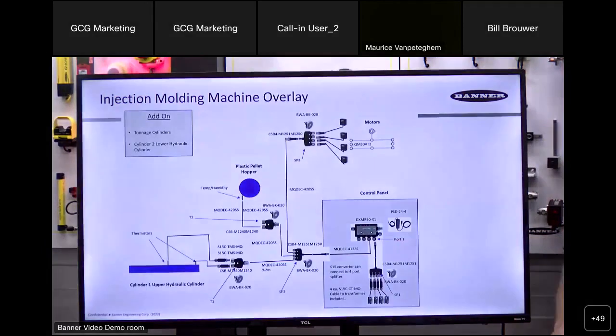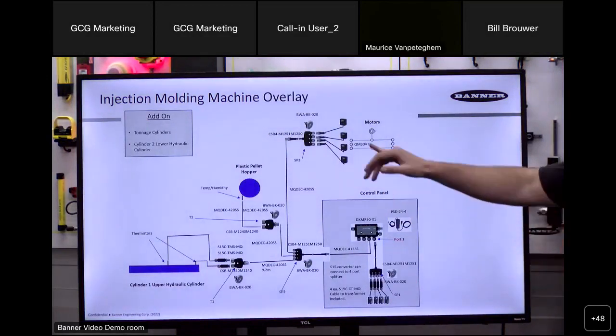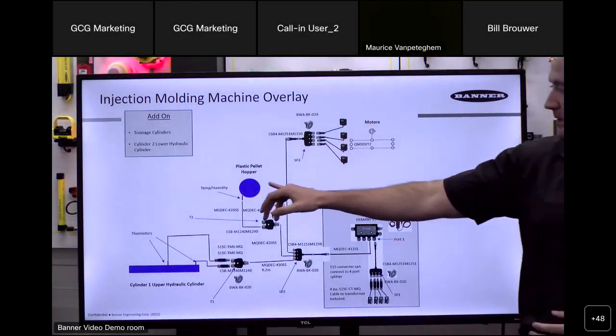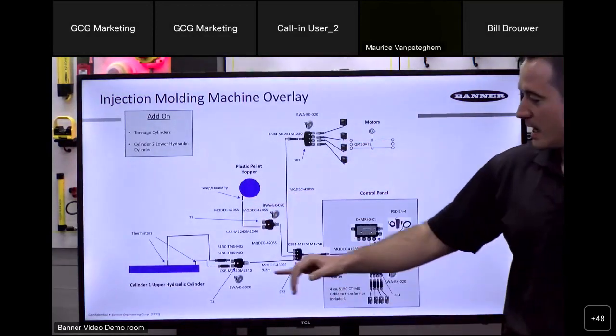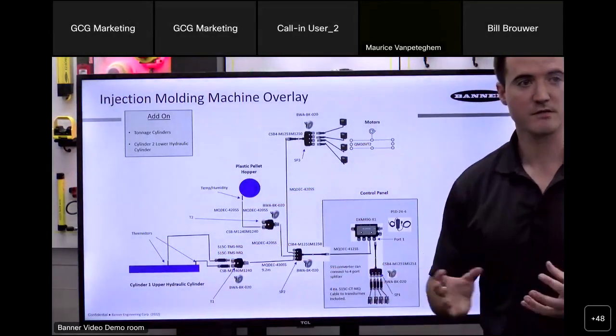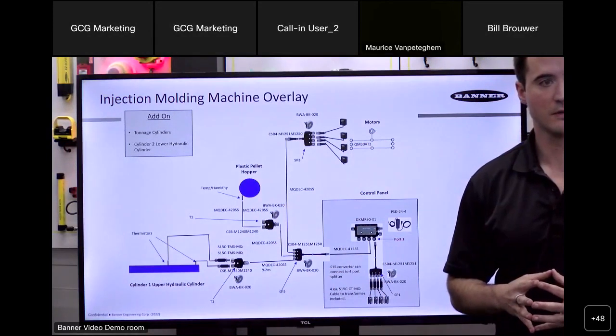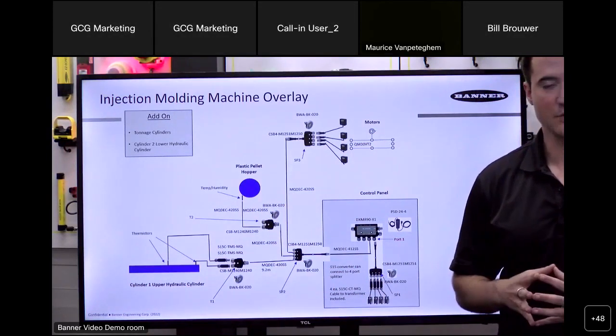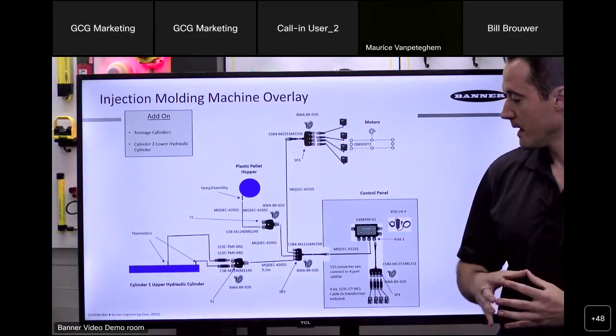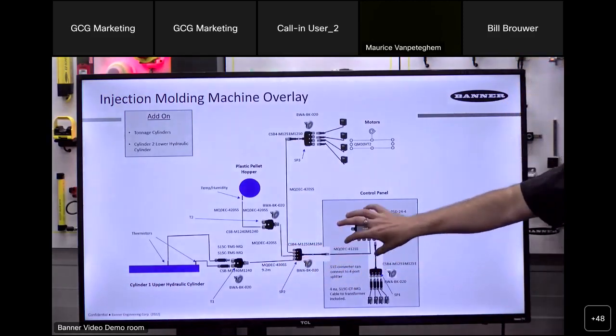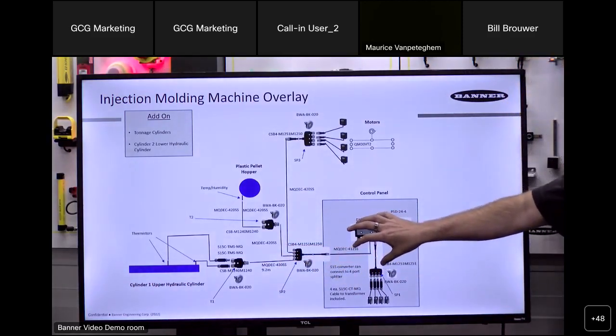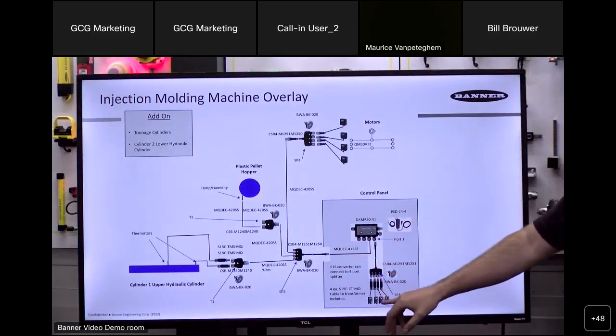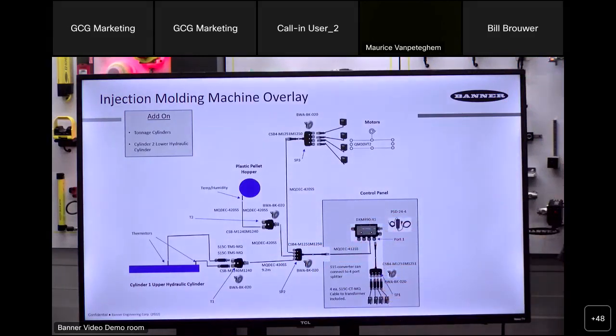We were able to plan out a system to monitor this type of process with Snap Signal technology - monitoring the motors, monitoring temperature and humidity in the hopper, and using thermistors which we could convert to that unified serial protocol on the hydraulic cylinder. We connected this back to the DXMR90 deployed inside their cabinet, and in addition we had current transformers monitoring the motor.